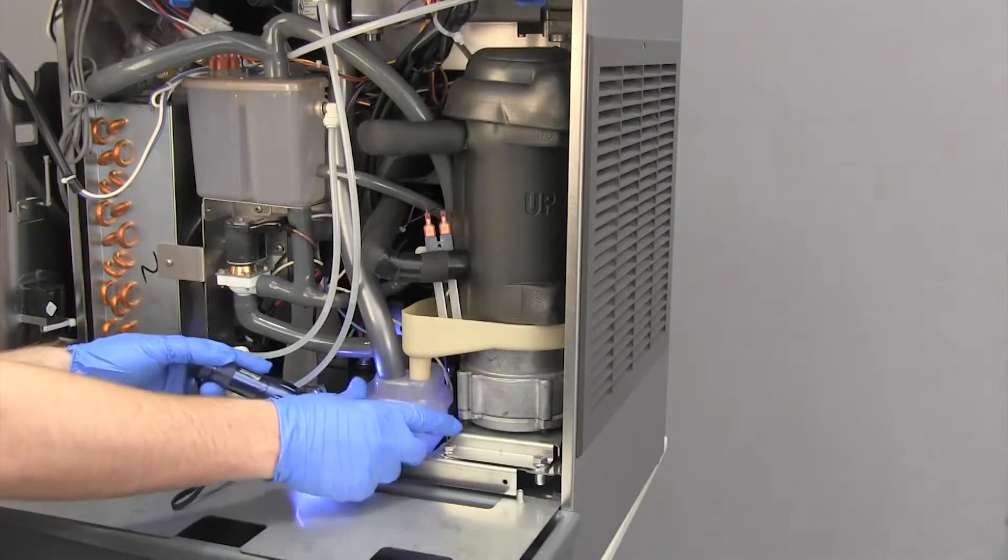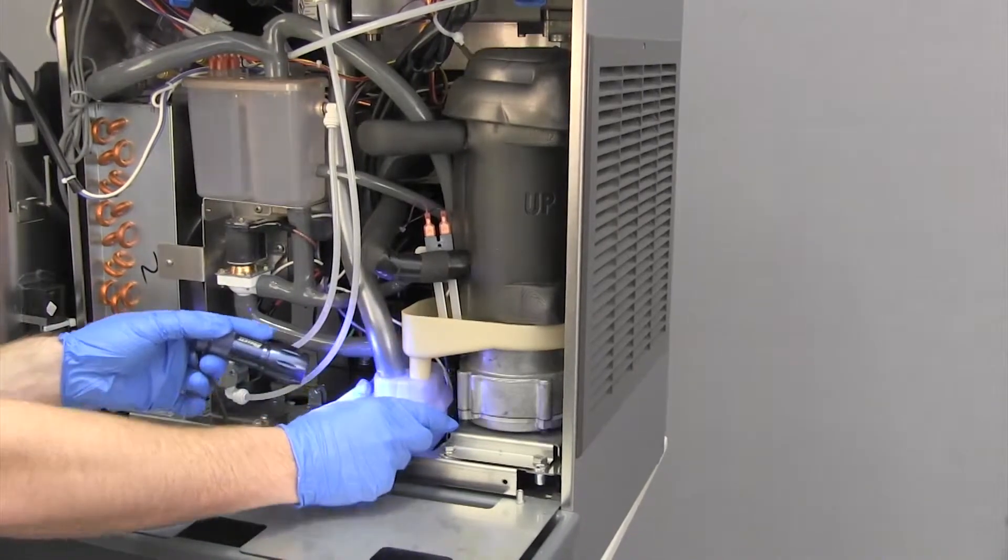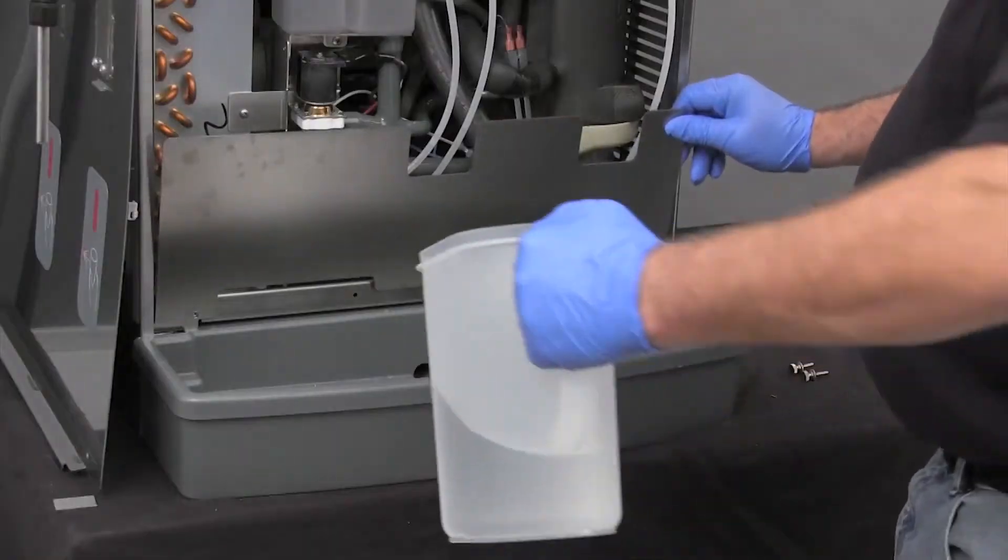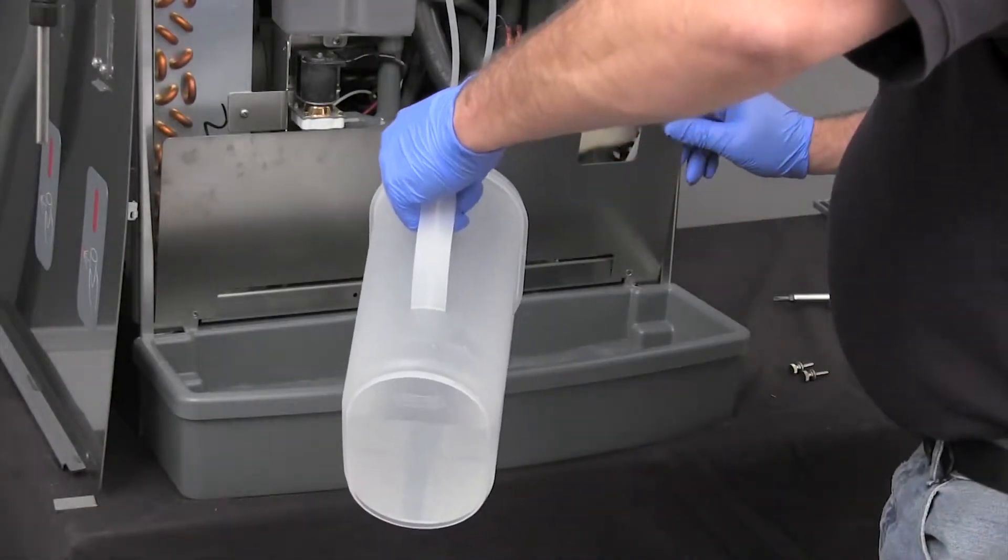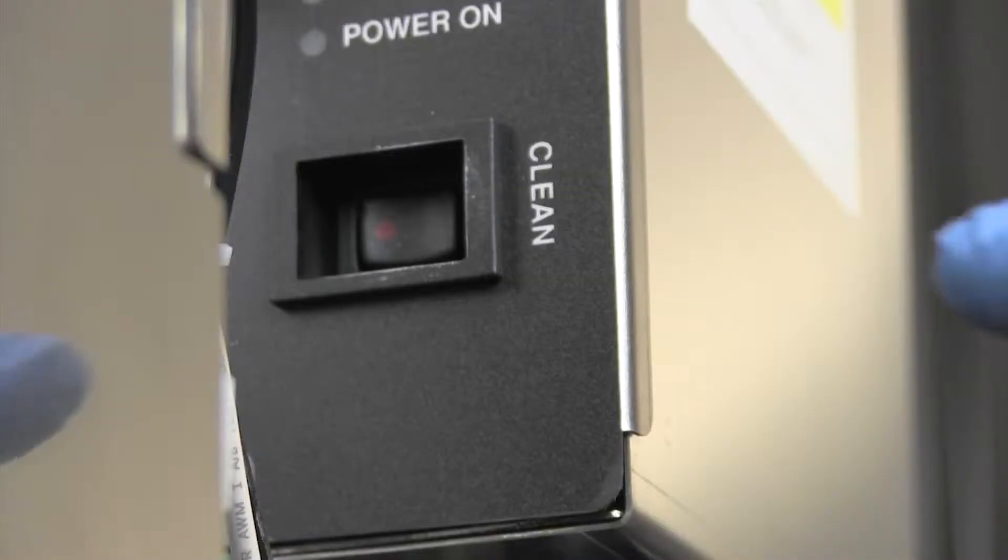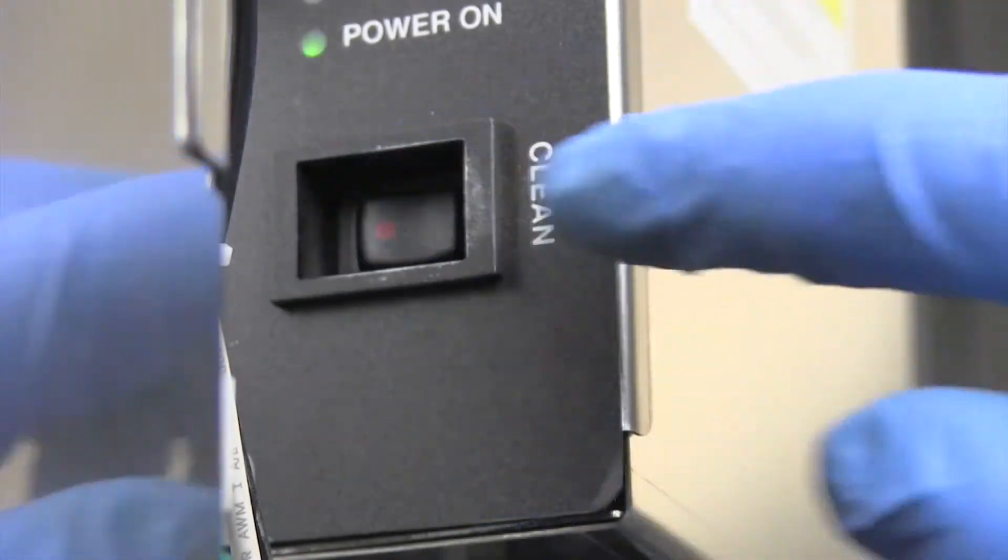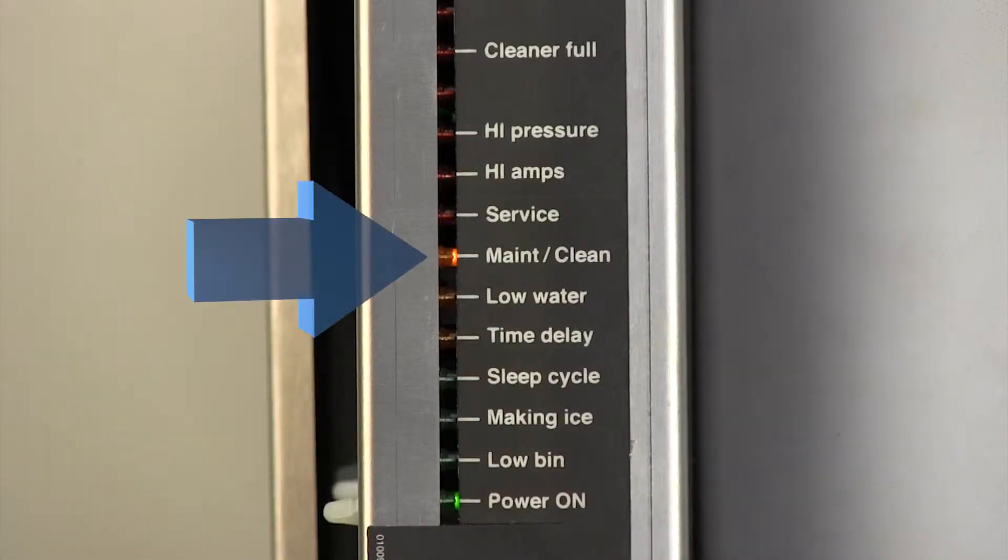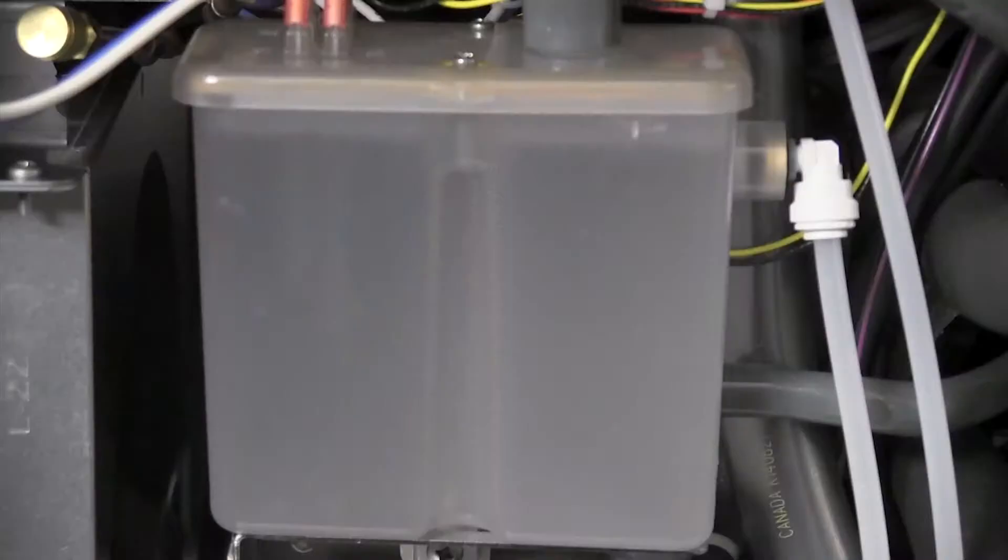Inspect the drain cup and check the drain pan drain line to ensure they are open and water can flow freely. This prevents potential water overflow during the semi-automatic cleaning. Start the semi-automatic cleaning cycle by pressing the clean switch. The maintenance light will come on and the water system drains.